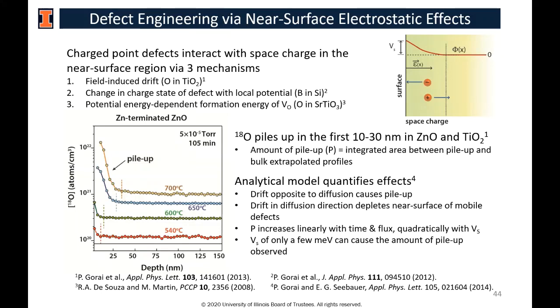A high sputtering beam can produce significant intermixing of the surface layer, destroying near-surface structures of interest. However, a minimum energy is needed for SIMS analysis. In TOF-SIMS, a unique solution is to use a high-current but low-energy 2 to 3 kilovolt cesium beam for material removal, and a low-dose but high-energy gold beam for SIMS analysis. This experiment explores charged point defects in the near-surface region on bulk diffusion of a biased sample, where samples were annealed in natural abundance O2 and then in isotopically enhanced 18-O2, allowing determination of the amount of surface pileup of 18-oxygen due to band bending.